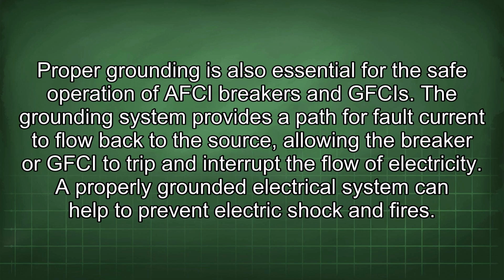Proper grounding is also essential for the safe operation of AFCI breakers and GFCIs. The grounding system provides a path for fault current to flow back to the source, allowing the breaker or GFCI to trip and interrupt the flow of electricity. A properly grounded electrical system can help to prevent electric shock and fires.